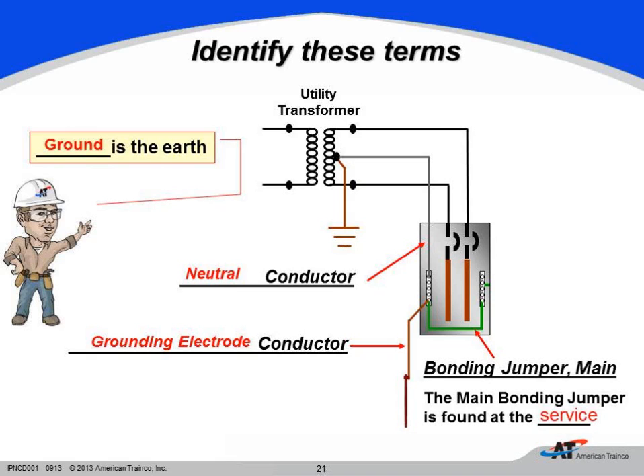Well, the grounded conductor, of course, is going to be white, gray, or 3 continuous white stripes, and this year in the 2014 code, they are allowing us to have 3 continuous gray stripes. So they changed that up a little bit, but I would also explain to everybody that sometimes the grounded conductor is also the neutral. In this little diagram, you can see that it is bonded to the midpoint of that single-phase transformer, and in that case we can call it a neutral, but it's also a grounded conductor. So we can see that this just helps us a little bit with terminology.